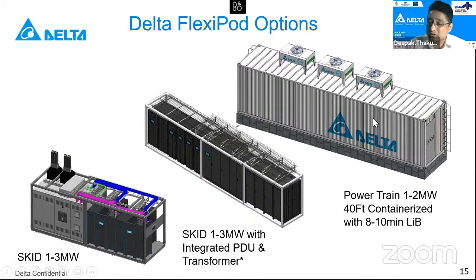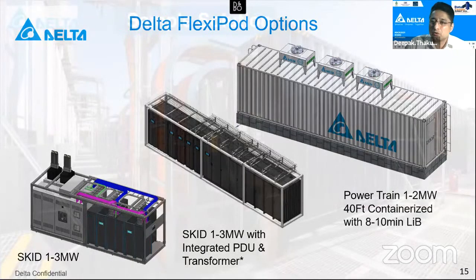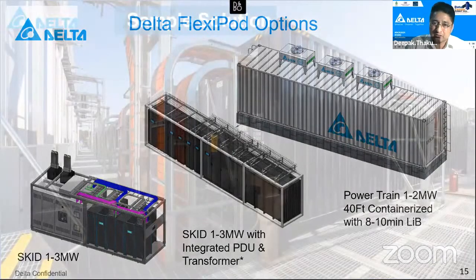And then, of course, when you go to the edge side or to larger outside horizontal expansions, you have power containers of 1 to 2 megawatts in 40 feet containers with 8 to 10 minutes of LIB battery inside the entire container. So this is one of the unique things which we can offer. As an example, we have deployed over 100 of these 40 feet containers at one of the large colo players in Asia Pacific, with lithium ion batteries and around 5 to 6 minutes of backup inside.